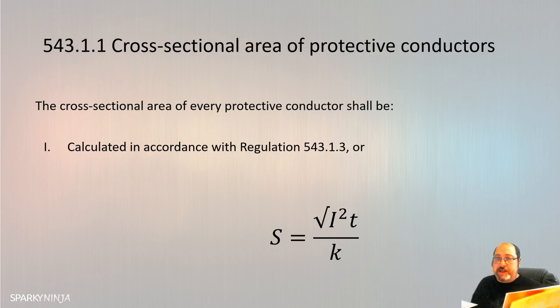Again, in this case, you can see clearly that a type C MCB was a lot more effective. But you may also notice, though, that you did require quite a large amount of current on that circuit breaker. 450 amp, really, was what was required to achieve this disconnection instantaneously, whilst only 145 amp was needed to achieve the 5 seconds for the 3036. So that's an example of calculation.